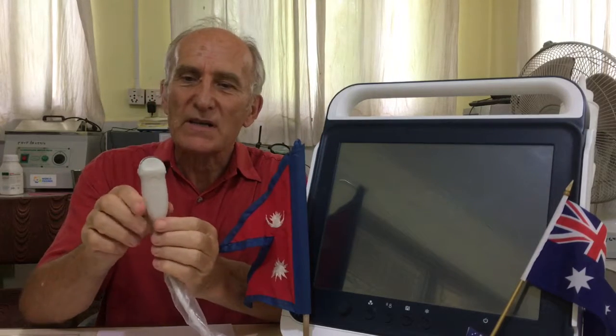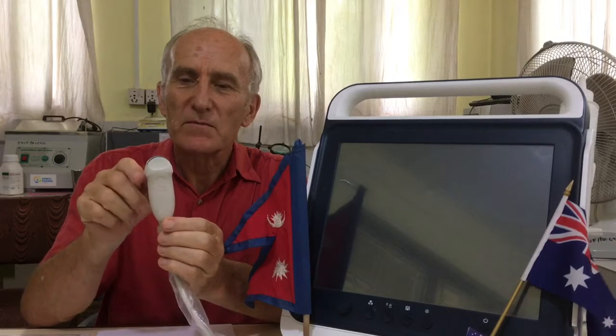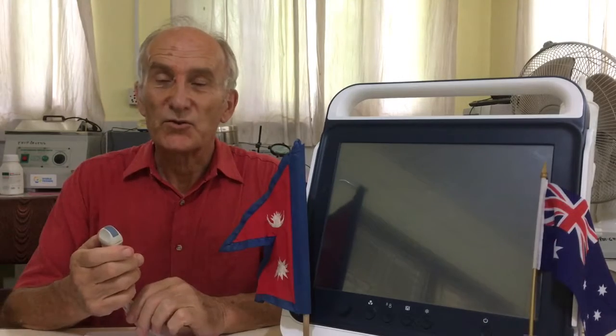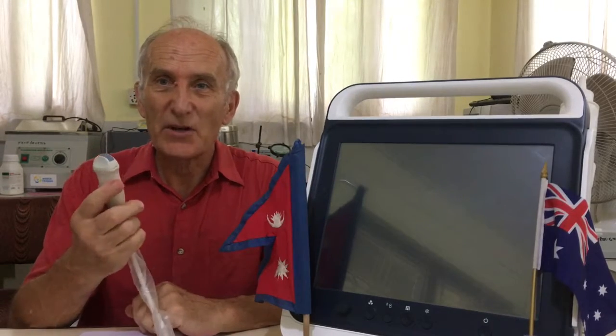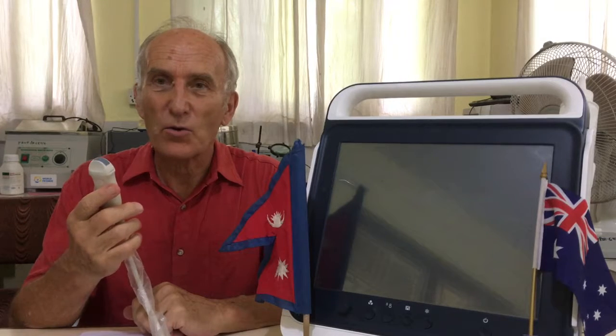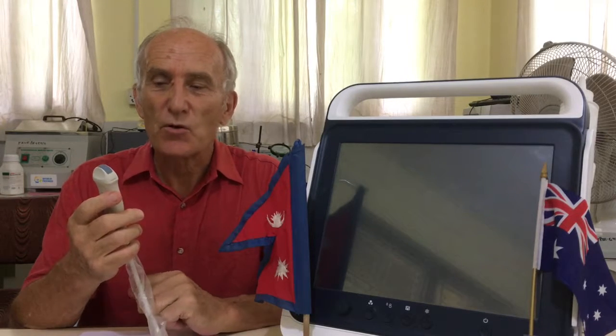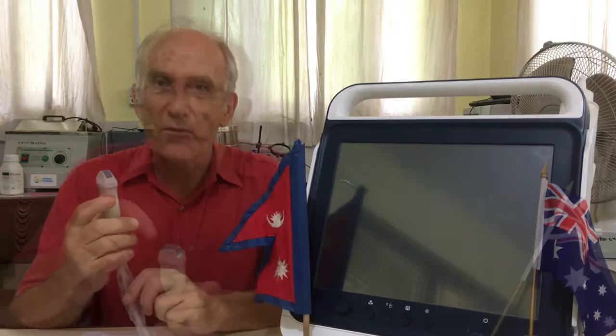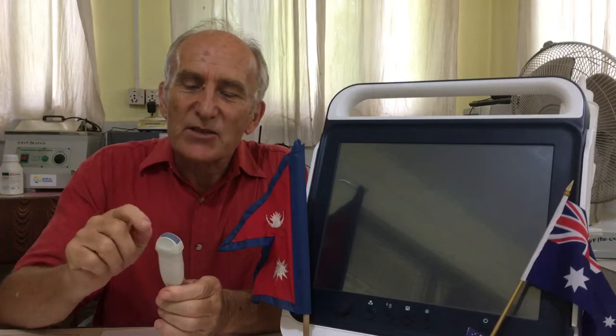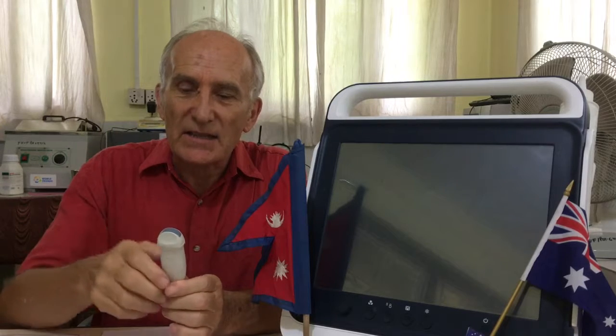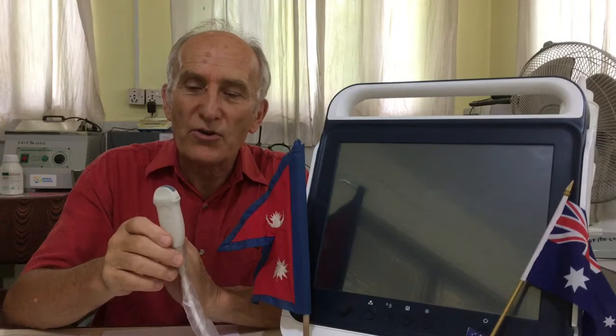Now the probe is a curved probe. It's very delicate. Do not immerse the probe in any liquid, any alcohol or any water, but after use wash it with a soapy cloth. The grey area here is where the ultrasound is produced and collected. So this is called a probe or transducer.